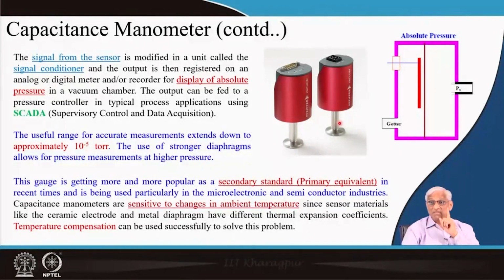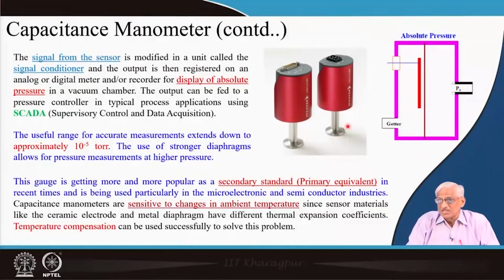It should also be very fast. In a load lock chamber in a semiconductor industry, you load the wafer, immediately do some cleaning operations, and transfer it to the main chamber for growth. During this time, you must data log very fast that it has reached that pressure. So these gauges are rugged and useful. Some gauges may be faster but not rugged - a thermocouple gauge or Pirani gauge, after some time, will measure something else and are not reproducible. This gauge has its own merits.